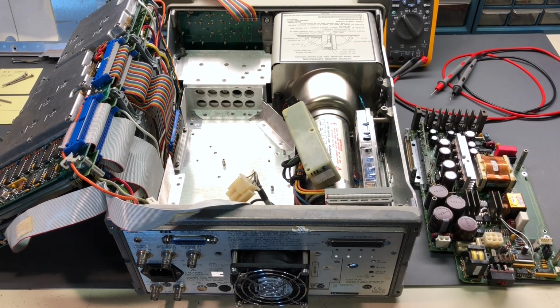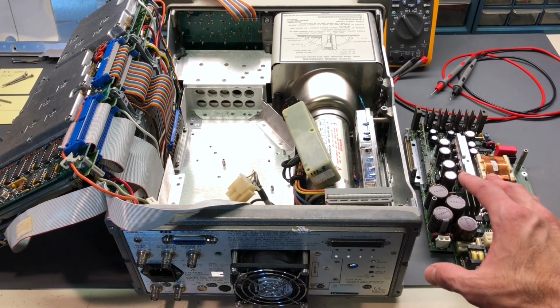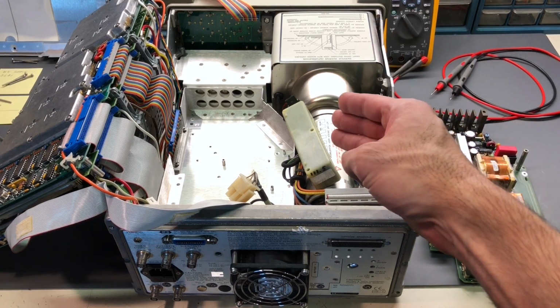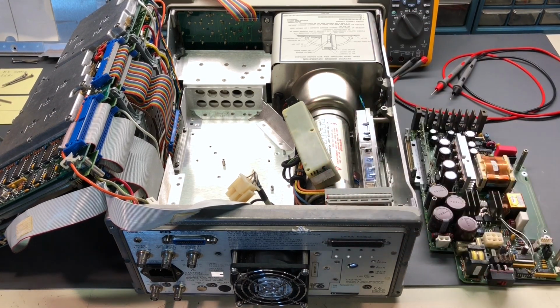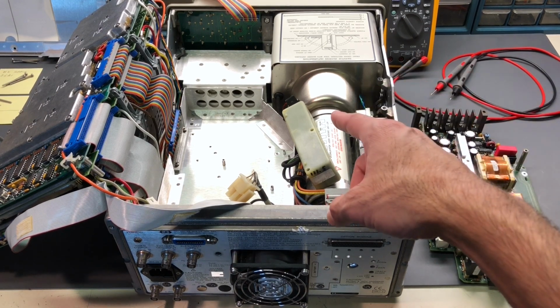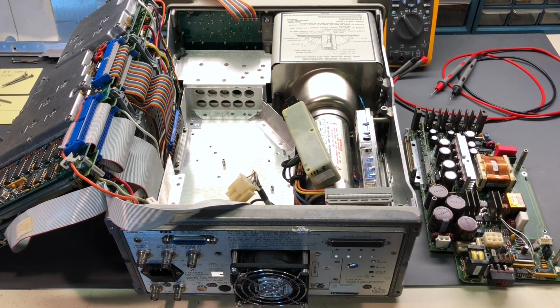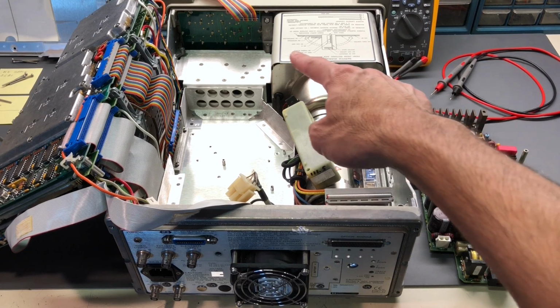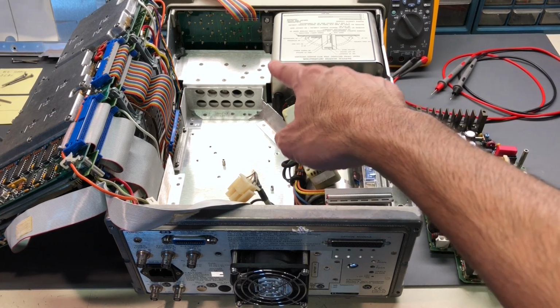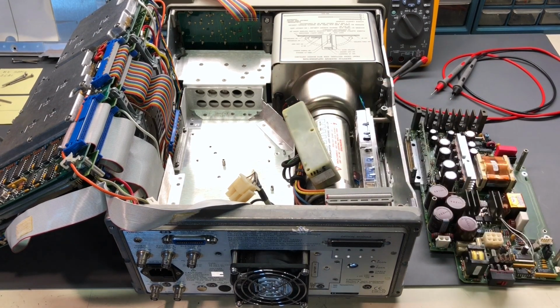Now if you're following along and working on an instrument like this, you are doing so at your own risk. You need to be aware of the dangers involved with the high voltage on this circuit board, as well as the cathode ray tube, or the CRT, and this high voltage module right here. The CRT can retain a charge long after the instrument is powered down. The anode of this CRT operates at least 9,000 volts, and again that charge can remain for quite some time. The anode comes out under this metal shield. There's an opening over on the side over here, and then there's a rubber boot on the wire lead.